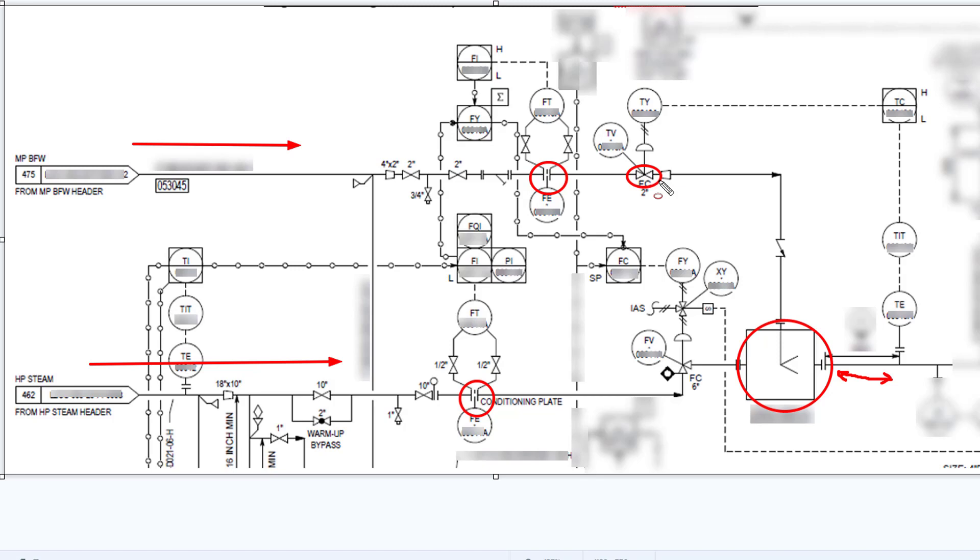It looks fine and typically this is what you see. But what happens in practice is this design doesn't work. I have to explain mathematically why it doesn't work from a simple heat and material balance, and how one can improve the design so that it can operate through an entire operating region. A lot of the cases that aren't considered during startup: you don't really have this valve, and this steam valve is only partially open. Often there are minimum bypass lines around here, sometimes there is minimum steam going through just to keep this unit warm. There's not real flow control here.